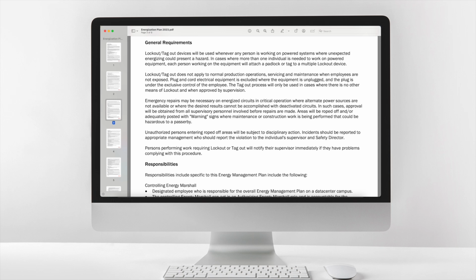Emergency repairs may be necessary on energized circuits in critical operation where alternate power sources are not available or where the desired results cannot be accomplished with deactivated circuits. In such cases, approval will be obtained from all supervisory personnel involved before repairs are made. Areas will be roped off and/or adequately posted with warning signs where maintenance or construction work is being performed that could be hazardous to a passerby. Unauthorized persons entering roped-off areas will be subject to disciplinary action.